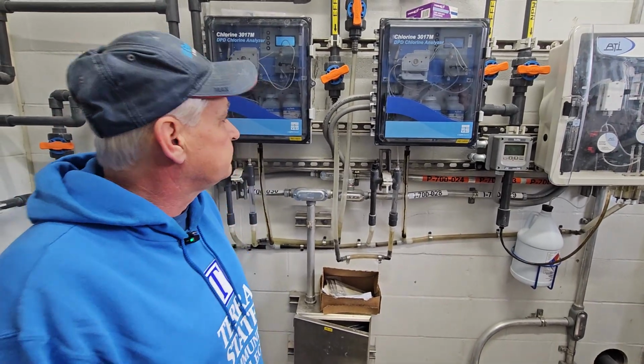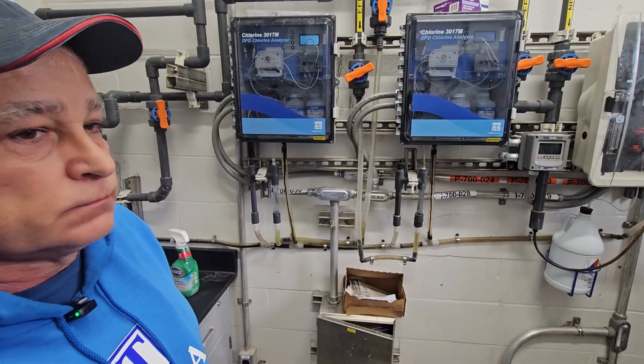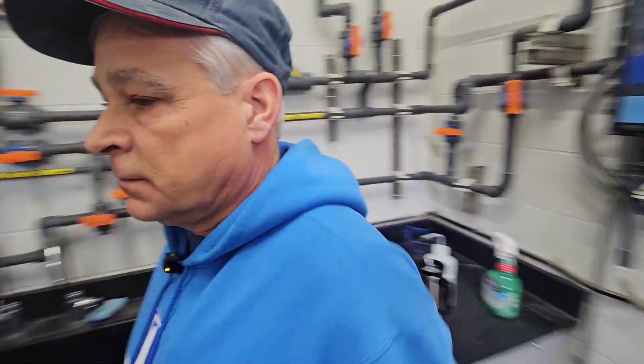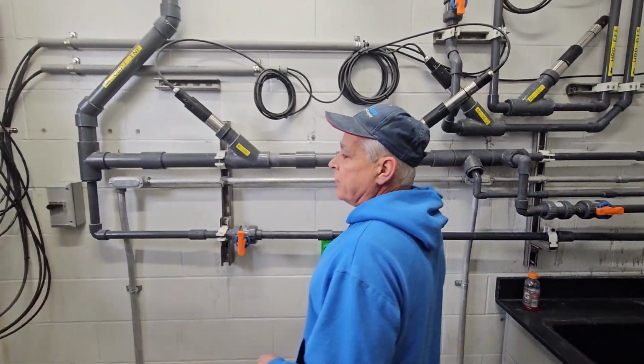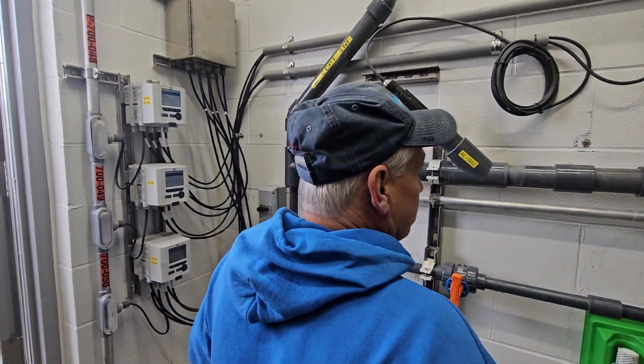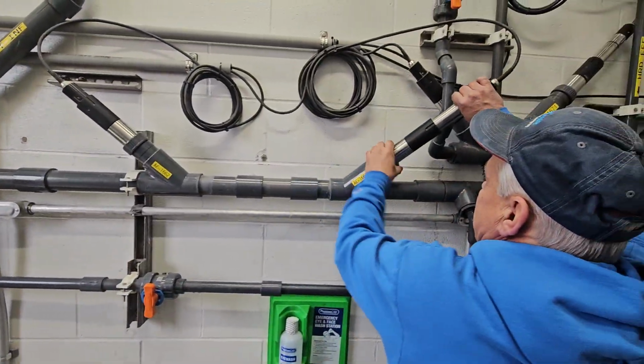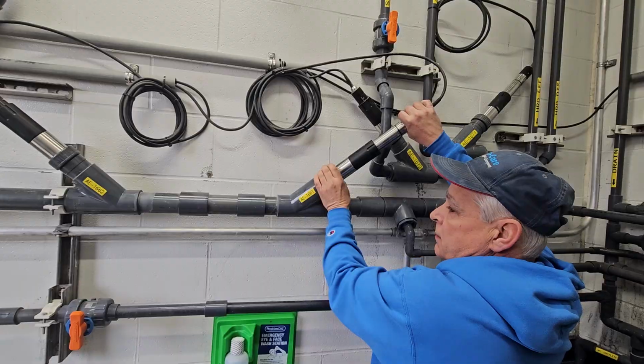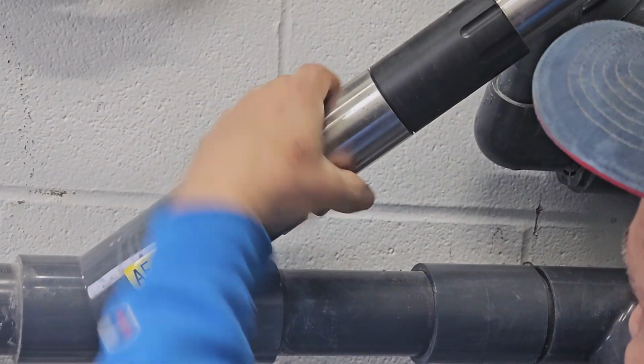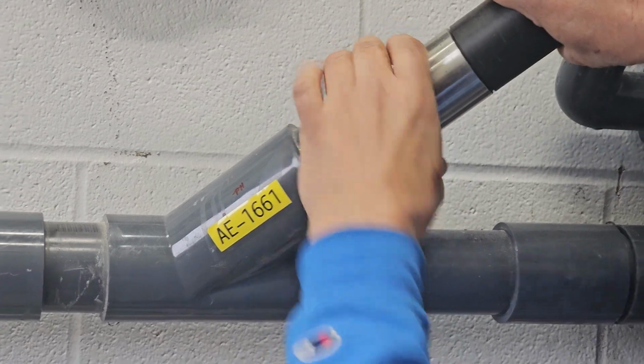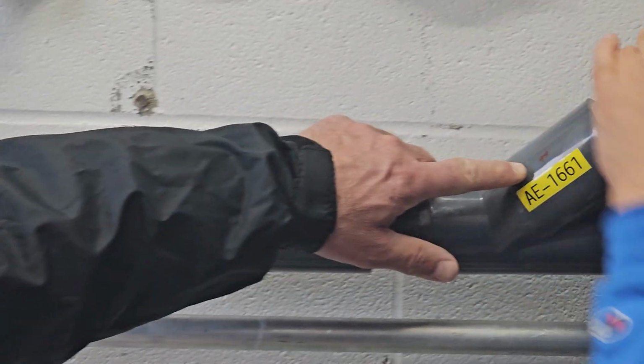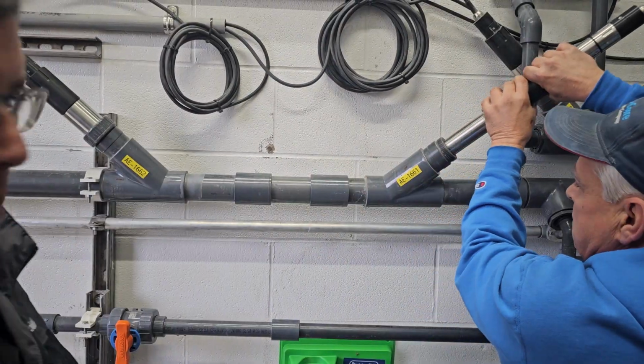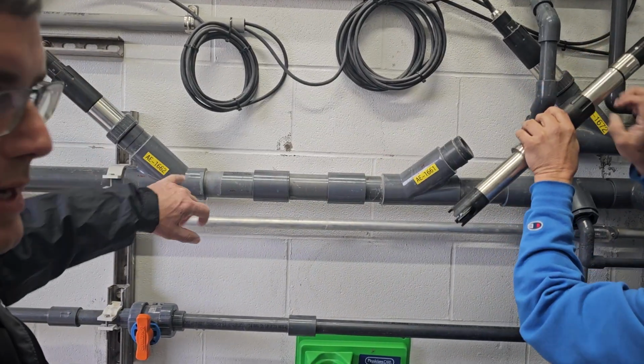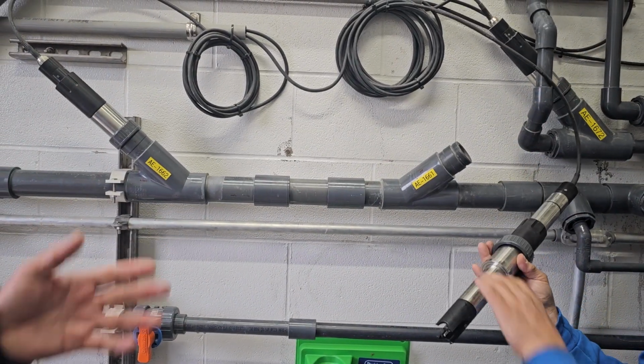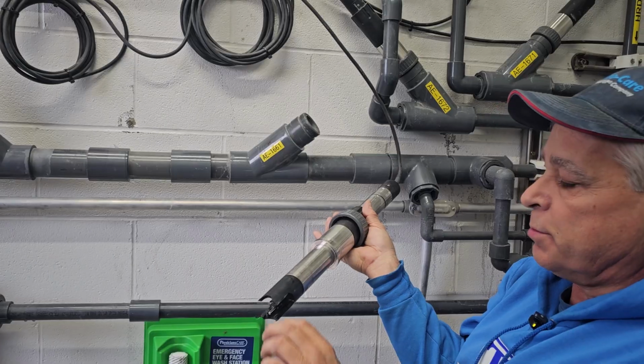Okay, can we go over the probes behind us, removing and cleaning them? Yes. See over here are the controllers for the pH and the turbidity, and we've got nuts that we loosen to take them out of the process piping. We discussed putting labels, like writing pH here, so we're going to grab the labeler and put pH and turbidity by those labels so you guys know which one's which easier. So the probe comes out.